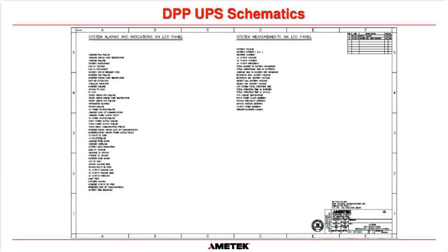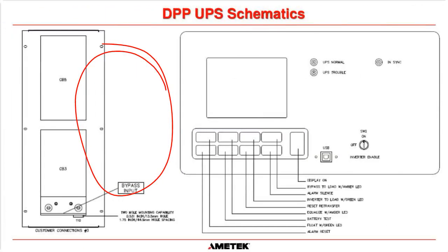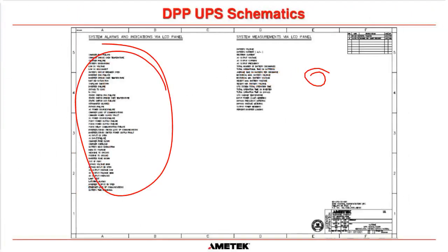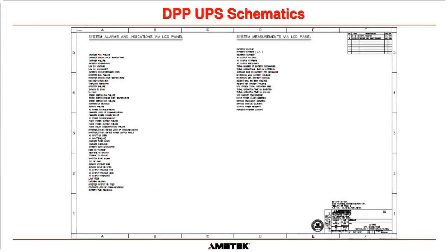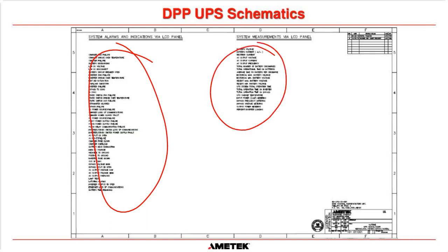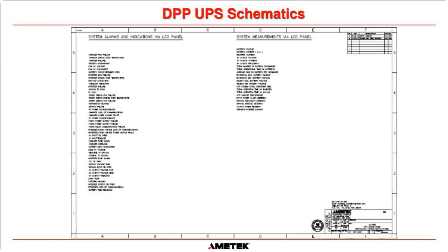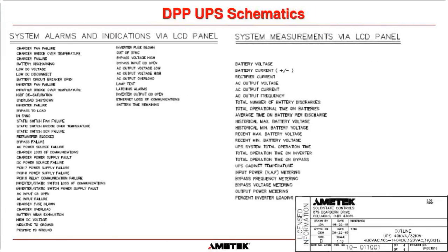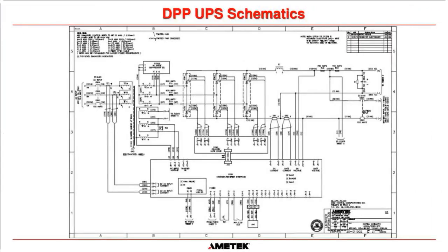And this describes all of the alarms that will alarm on your Mimic screen and will report to the DCS on the common alarm. So if you got an alarm on the system, if we go back, if we got this UPS trouble alarm, what this is saying is it must be one of these alarms that caused that trouble alarm. And these ones here, obviously, as well. They are all the options that have been enabled on this particular UPS. And that's it zoomed in so you can read them. Okay.